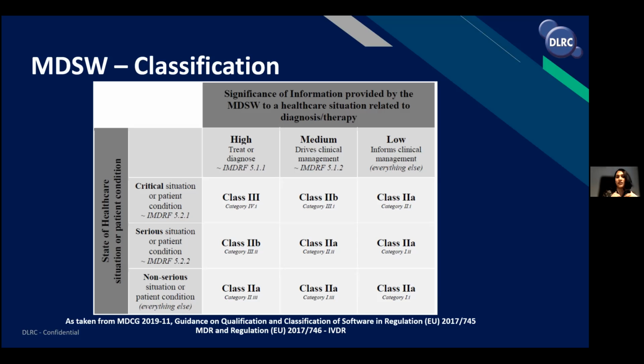So it's based on the significance of information that's provided by the software, and then it's compared to the state of healthcare or situation or the patient condition. So in this case, because our device is not really doing anything, but it's just identifying and localizing areas of interest, which then need to go to a clinician who will then make a decision on whether this patient has a specific condition, it's defined as informing clinical management. So you can see here that even for critical, serious, and non-serious situations, every time it'll be classed as a class 2A. Now, if our device was to do a little bit more, so for example, it was to say that based on an image you either had a condition or you didn't, then it's potentially driving clinical management, and therefore we would classify the device as either a 2A or 2B. But in our case, because it's only informing clinical management, it's class 2A.